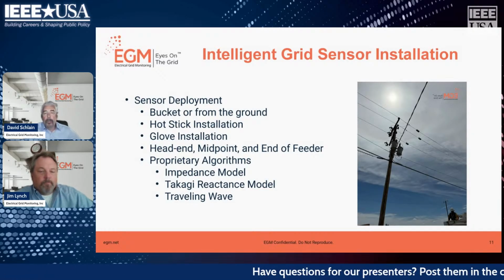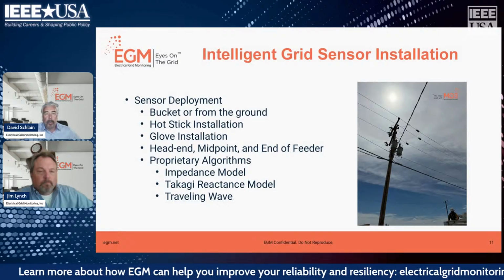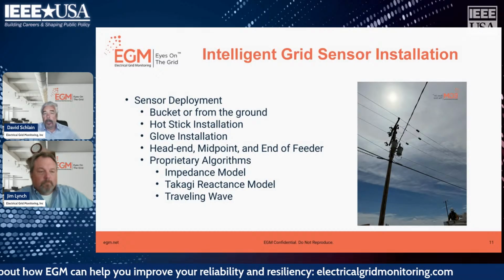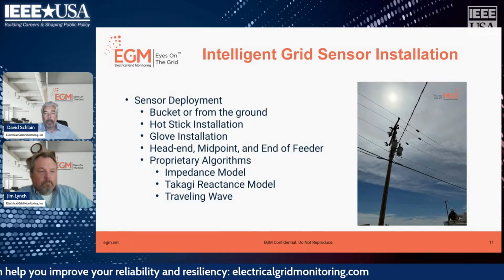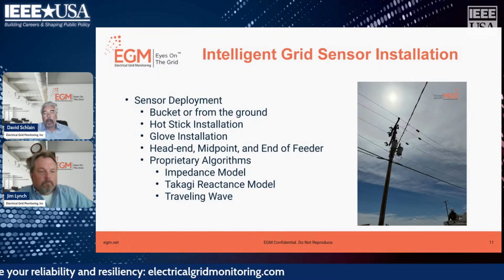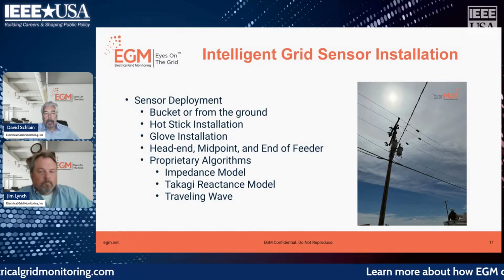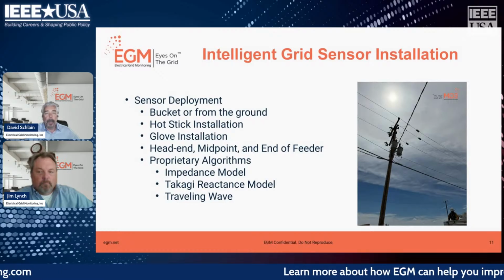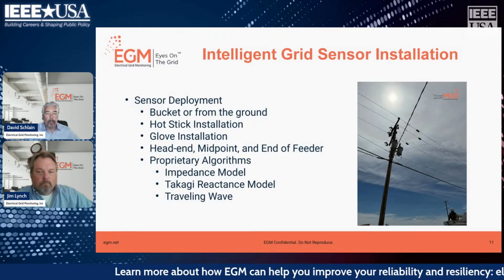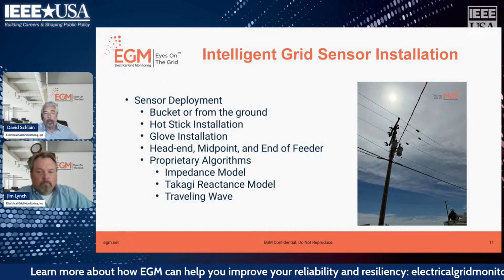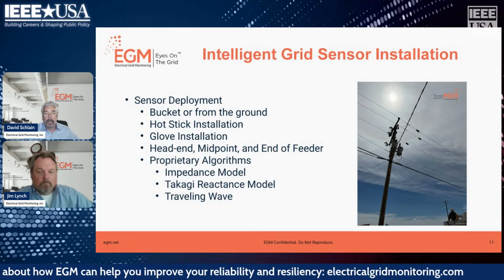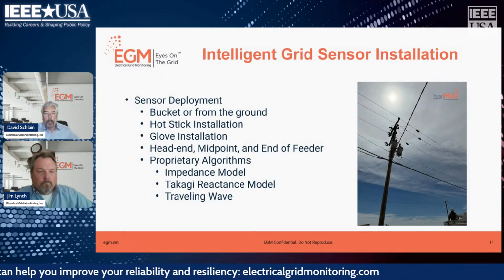These sensors are inductively powered from the line and made to last 10 to 20 years without any human intervention. They basically operate as line monitors sending data back to the platform. Once the sensors are hung and collecting and sending data back to the server, the platform runs fault location algorithms to help locate those faults.